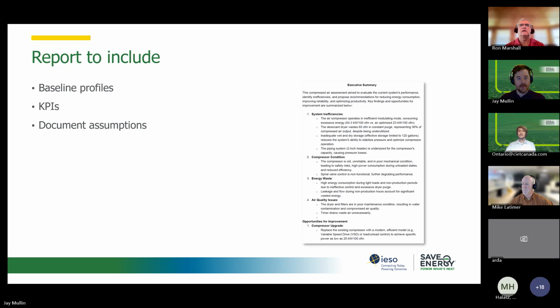Yeah, that's right. I've come across projects where at the end of everything, the power consumption was more than the original system. Because we documented all the assumptions and conditions, we could tell. It was one of those projects where they expanded the plant and increased their air load. So you can adjust based on those captured key performance indicators, and the system was much more efficient, but it consumed about the same amount of energy because they were consuming more flow because they had added an additional production line.